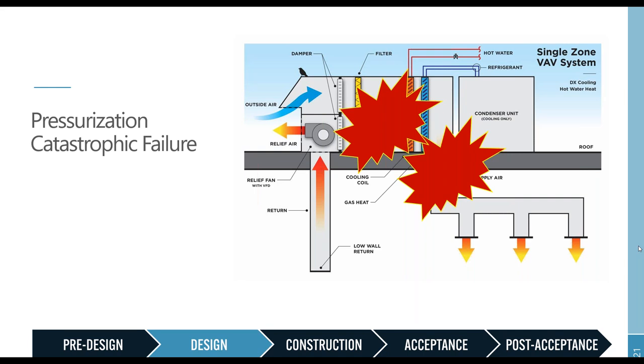And this came up as a sort of unplanned circumstance that towards the end of construction, the building that we were working on actually had an unplanned electrical outage. And what was discovered in this case was the generator came on as it was supposed to. The air handler continued to run and worked as intended. However, all of the terminal units, the VAV boxes down in the zone, we discovered were not actually on emergency power. So the controls closed all these boxes down.